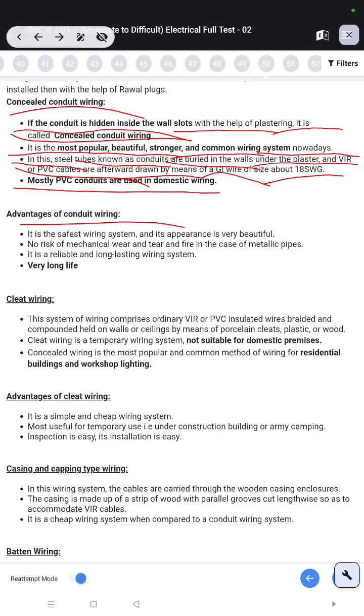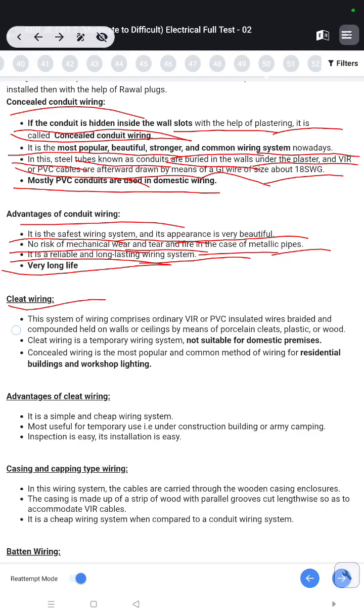Advantage of conduit wiring: it is the safest wiring system and its appearance is very beautiful. No risk of mechanical wear and tear and fire in the case of metallic pipes. It is a reliable and long-lasting wiring system. Cleat wiring. This system of wiring comprises ordinary VIR or PVC insulated wires braided and compounded held on walls or ceiling by means of porcelain cleats, plastic or wood. Cleat wiring is a temporary wiring system not suitable for domestic premises.